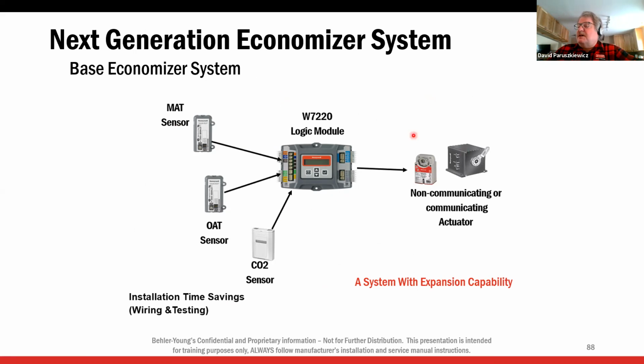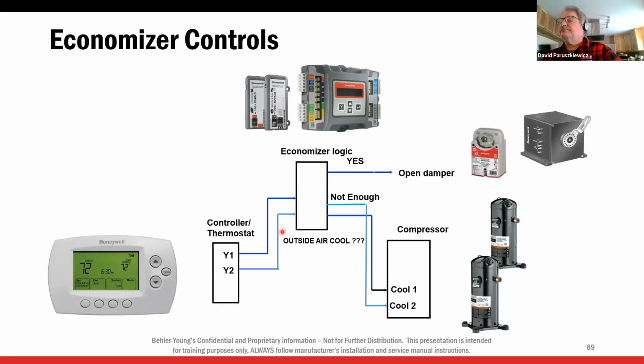All right, so here's the base economizer. There's the Jade module, our actuator, our mixed air sensor, 55 degrees by the blower. Outdoor air, again, in Michigan, we're always going to use the enthalpy sensor, not dry bulb. CO2 sensor, which is an option, much less used, and that's for fresh air. So again, how this is going to work. I get a call for first stage cooling. It goes to the Jade controller. The Jade says, hey, Mr. Enthalpy sensor, is it cool enough outside for outside air? Yes. Damper's open, compressor's locked out. No, damper closed, first stage compressor comes on.